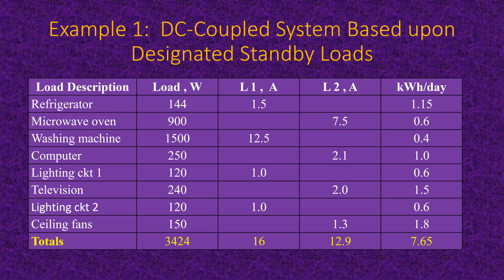Then there's the microwave oven at 900 watts. That's 7.5 amps, goes to line 2. Washing machine, 1500 watts. Maybe not 1500 anymore for the more efficient ones, but let's say it is. That would be 12.5 amps for line 1. Computer, 2.1 amps on line 2. Lighting, say you've got 120 watts of LED lighting.